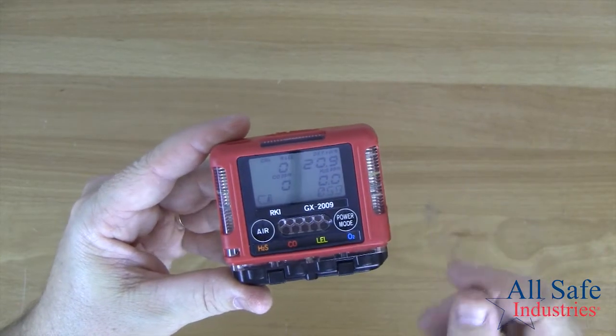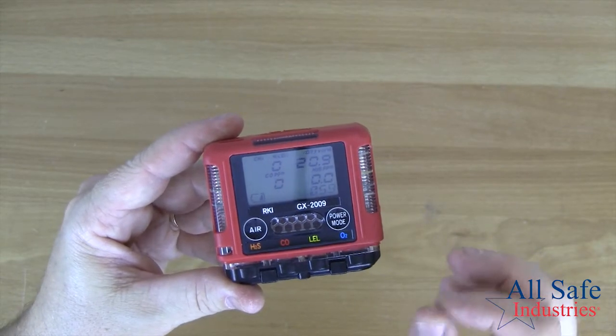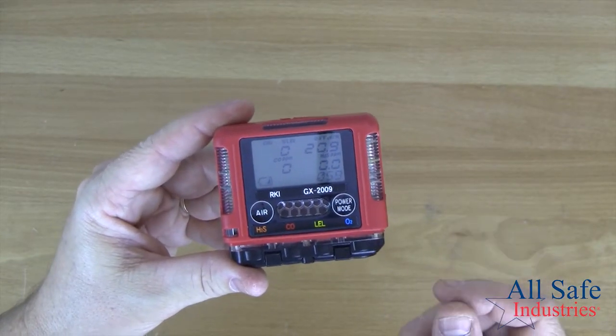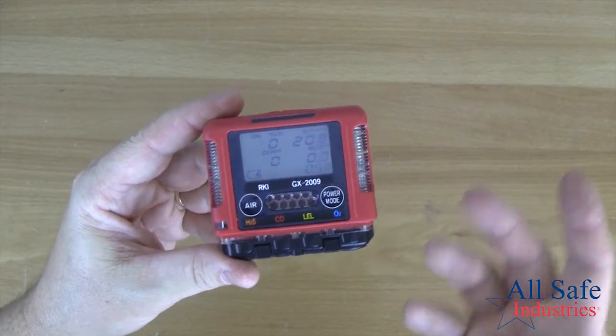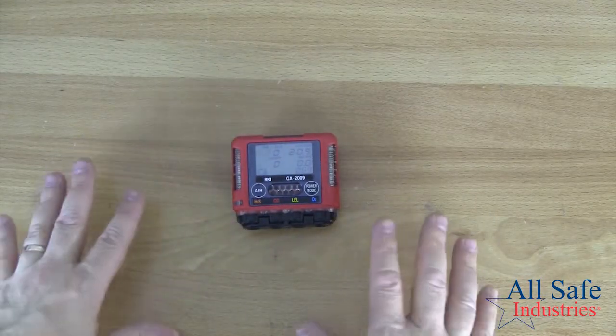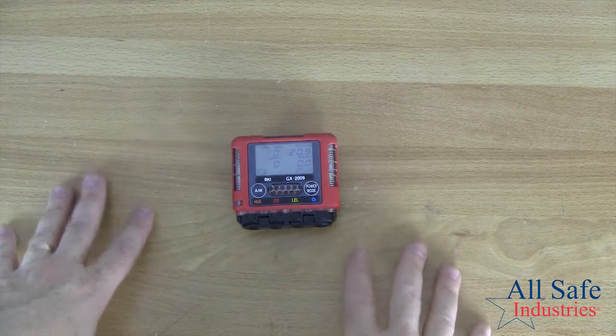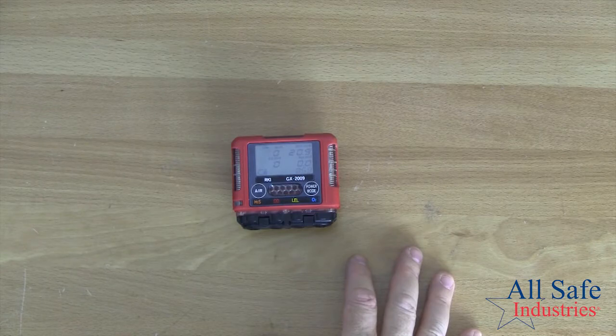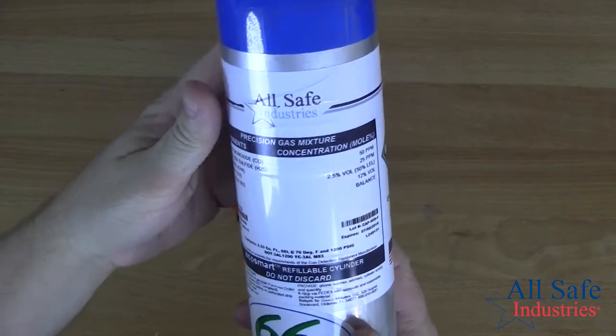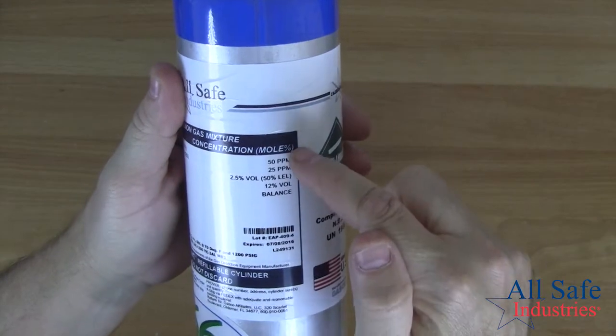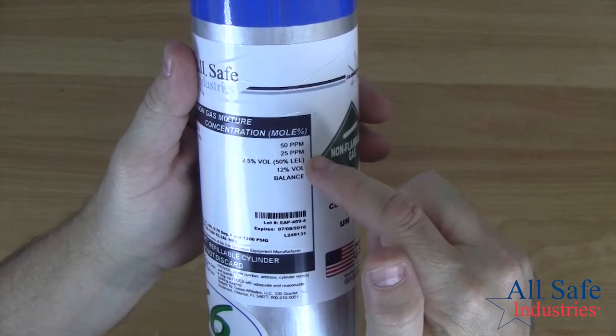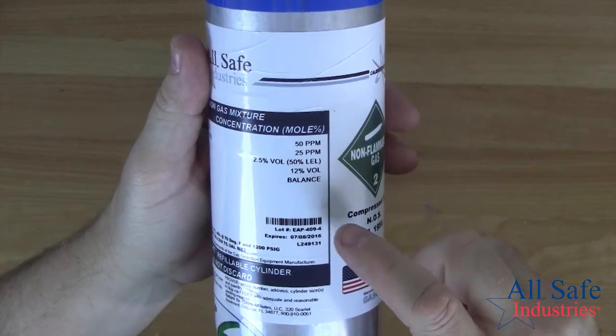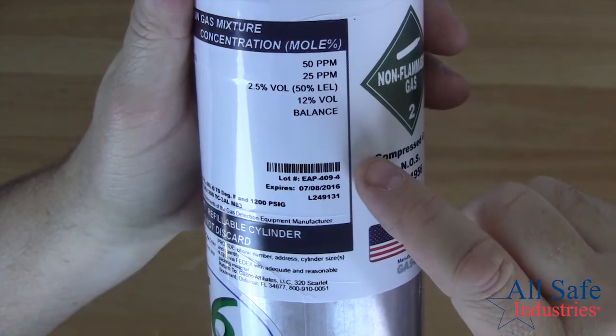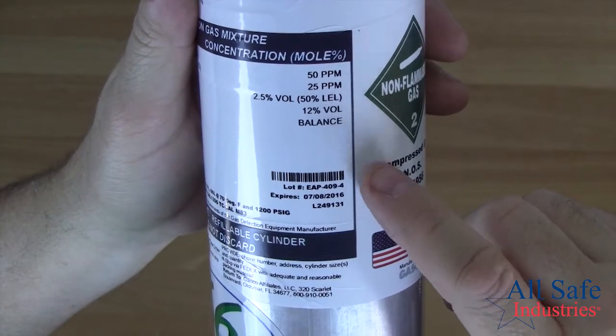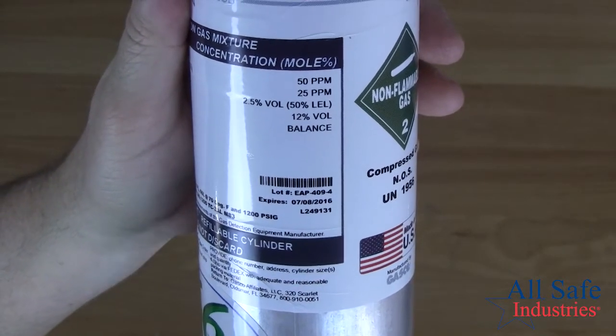So the next thing we need to do is see if the sensors are going to respond to gas in real runtime. And so the way we do that is by doing a bump check or a function test. If you read the book, the manufacturer says that you should bump check or function test your meter before each day's use. And so the way we do that is with the cylinder of calibration gas that came with your kit. You'll see that the gases are the right concentrations according to the manufacturer, and you also want to check the expiration date of your cylinder. If you have expired calibration gas, you want to replace that as soon as you can. OSHA would count that as a hit on your air monitoring program if you're using expired cal gas.